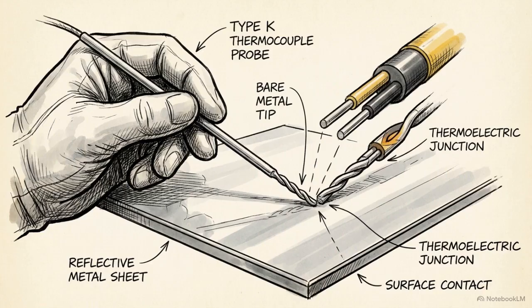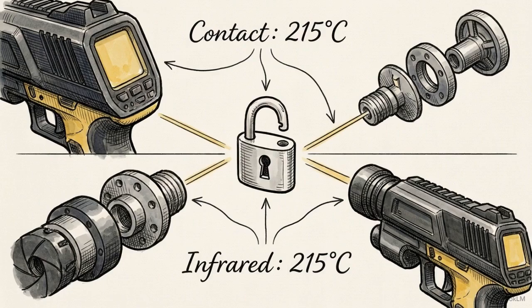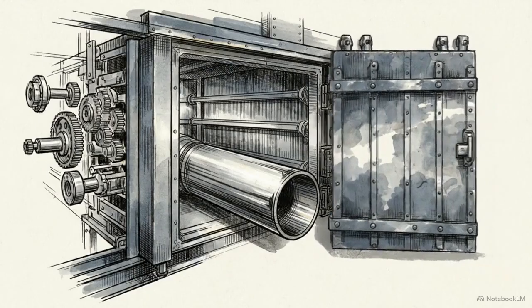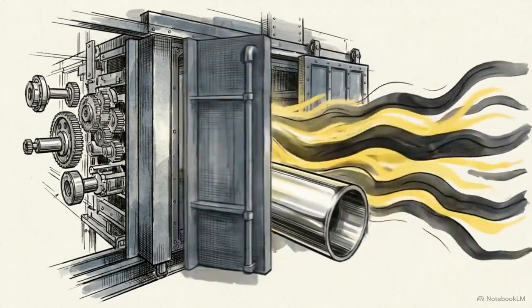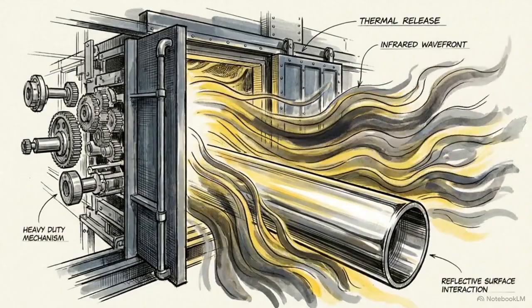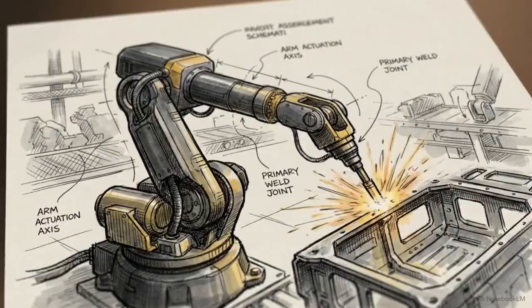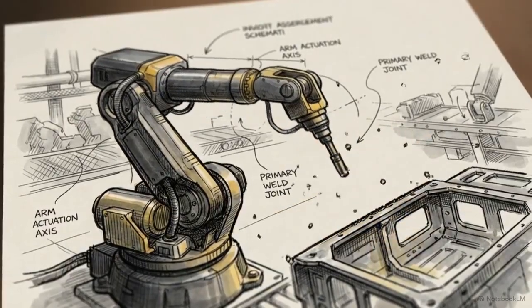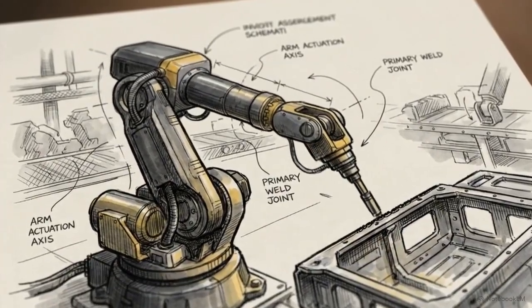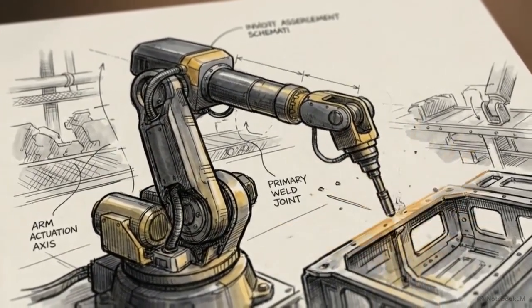For completely unknown materials, it includes a physical Type K thermocouple probe to execute a direct contact baseline reading, allowing the user to calibrate the optical sensor perfectly on the spot. This thermodynamic compensation ensures the detector is never fooled by environmental reflections, guaranteeing the captured data reflects the true structural state. Applied in the field, these exact thermodynamic tolerances dictate safety and continuous production across heavy manufacturing.